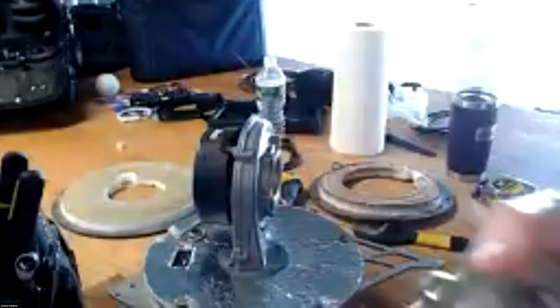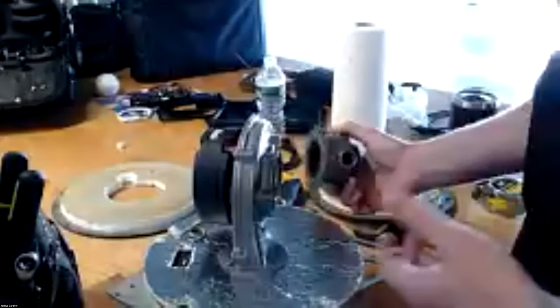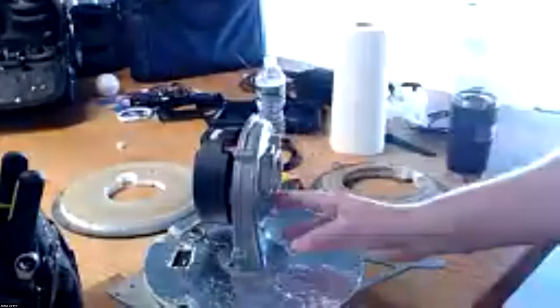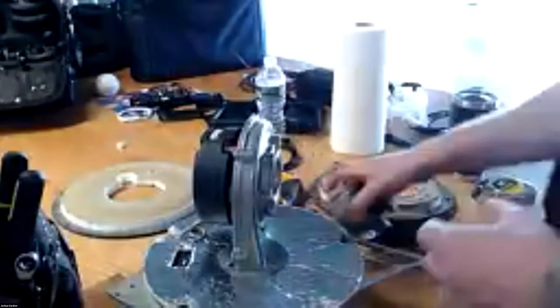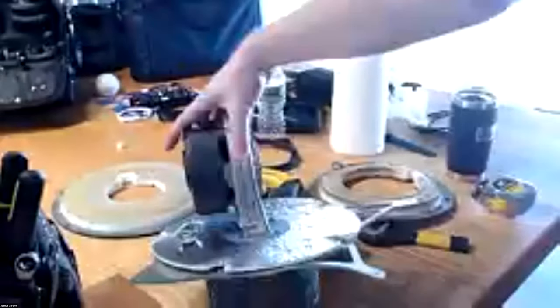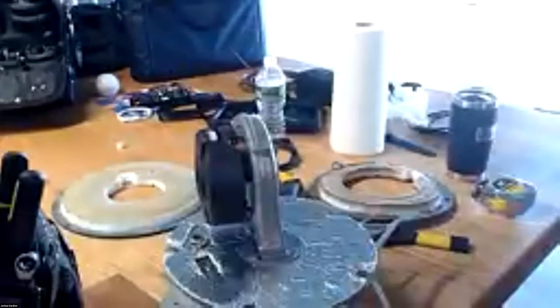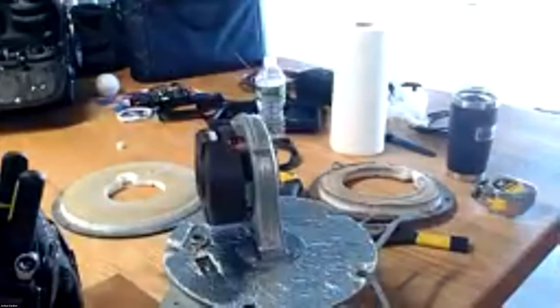We'll see discoloration and this plastic will get really brittle and could crack. Because as we're bringing in cold air and warm air, expansion and contraction, if this thing gets exposed to a lot of acidic condensation, that could be an issue. So I would inspect this, pop that back on there. If you change the venturi, it does come with the new O-ring here if you replace it. And yeah, that's pretty much pulling the heat exchanger and then putting everything back. You'll put everything back in. Let's just go ahead and reinstall that. And we'll hit on one little thing here.